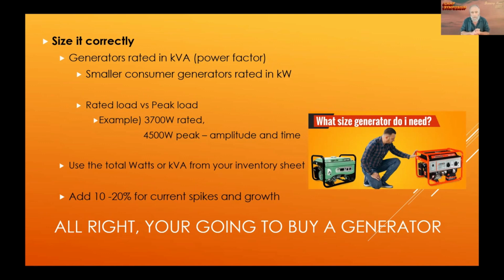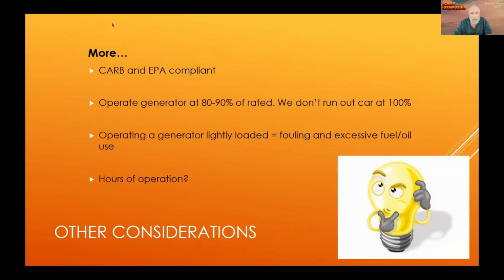If you're using the inventory sheet, you would utilize your watts and your kVA to figure out what size generator you're going to want. Consider also increasing it by 10%, 20% to deal with those voltage spikes or those current spikes, but also for growth, expansion in the future. We don't want you to expand, but you know, it happens. Also, more about generators. You want to make sure that they're CARB and EPA compliant. You don't run your car at 100%, so why would you run the generator that way?